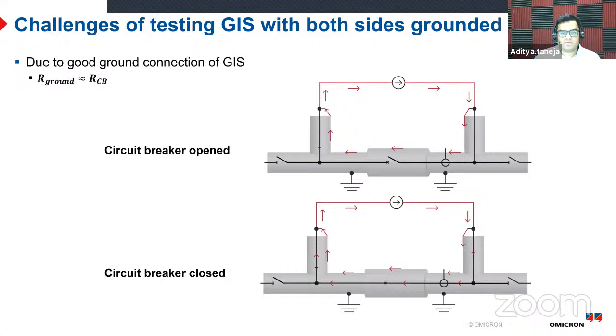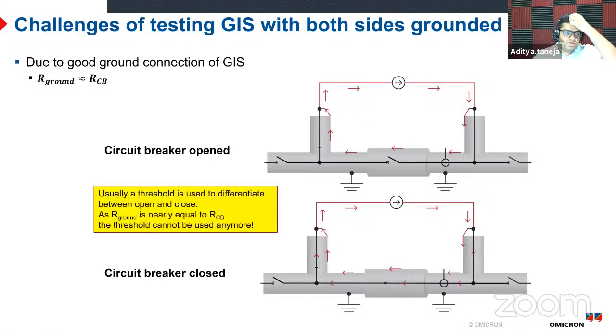And for testing, it creates a problem for us. Whatever signal we send for testing those breakers to know the main contact feedback, it will always get a feedback from the ground that the circuit is complete, because the ground is a very, very low resistance ground in a GIS. So we will never be able to use the conventional methods for knowing the feedback of the main contacts. Whether the breaker is open or closed, ground is always connected, and its resistance is comparable to the contact resistance of the breaker. So yeah, the conventional methods cannot be used.